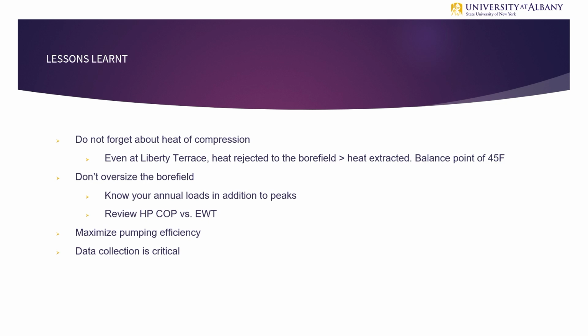The other thing is designing what range of temperatures you are designing it for. Heat pump COP, if you look at the curves for the heat pump COP versus entering water temperature, it's super important to understand that, because your COP might suffer a tiny bit based on the entering water temperature, but maybe that would help you downsize your bore field. So you have to look at those pros and cons to figure out what is the right size for the system. Maximize pumping efficiency. Once you've got a really efficient heat pump system, the COP can be 4 in heating compared to like 0.95 from a condensing boiler. So once you get to that high efficiency, pumping energy all of a sudden starts to become a pretty big part of the pie. So looking at your minimum flows, your bypass, making sure that you're not over pumping through the bore field, is critically important.